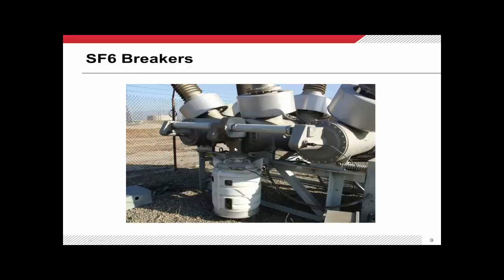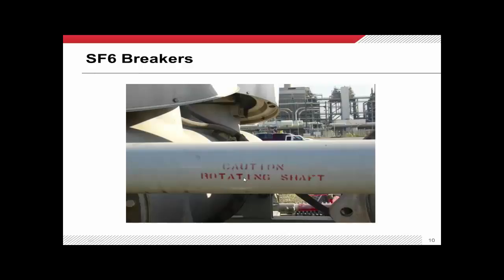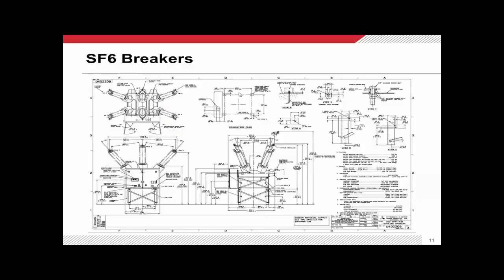That means the overall circuit breaker can operate in roughly two cycles, which is about the time frame we need it to operate. The spring releases its energy and you can see there's writing on this bar that says 'Caution: shaft rotating.' That's how it actually makes the three poles operate.